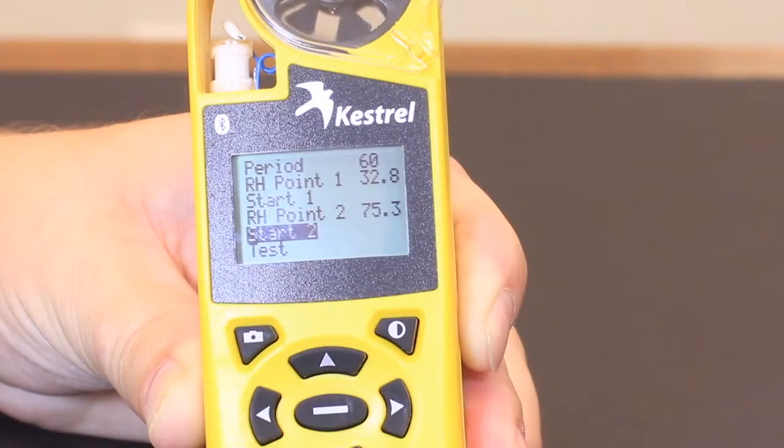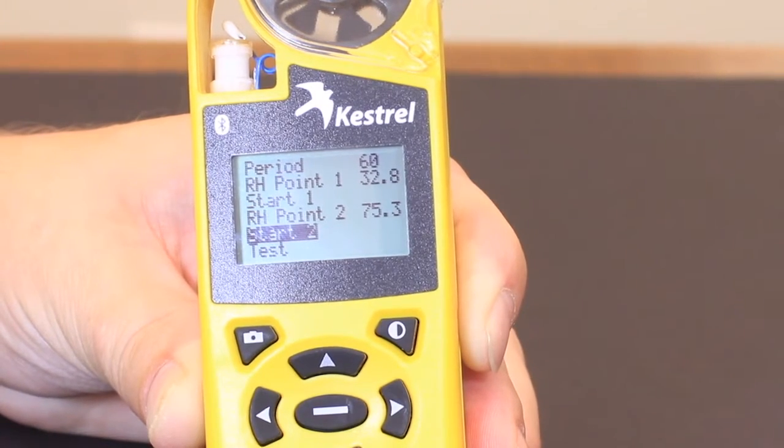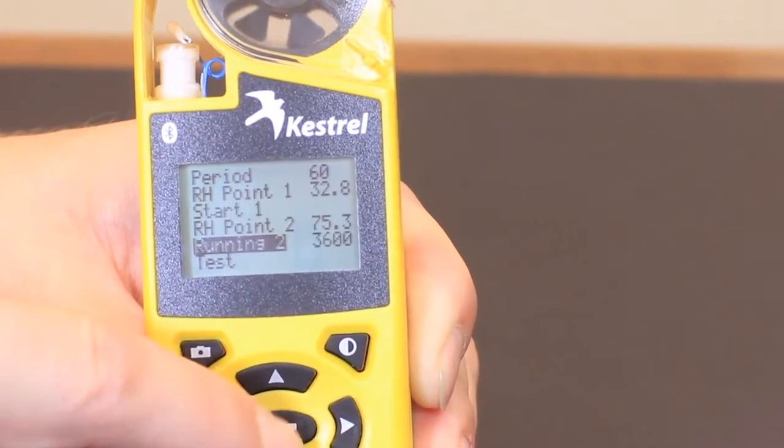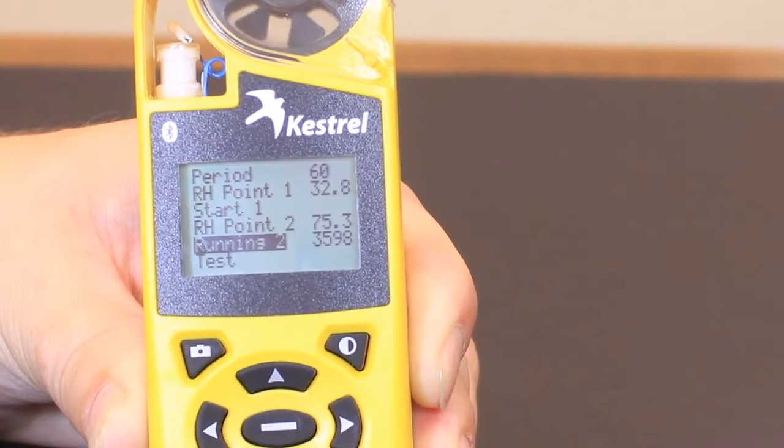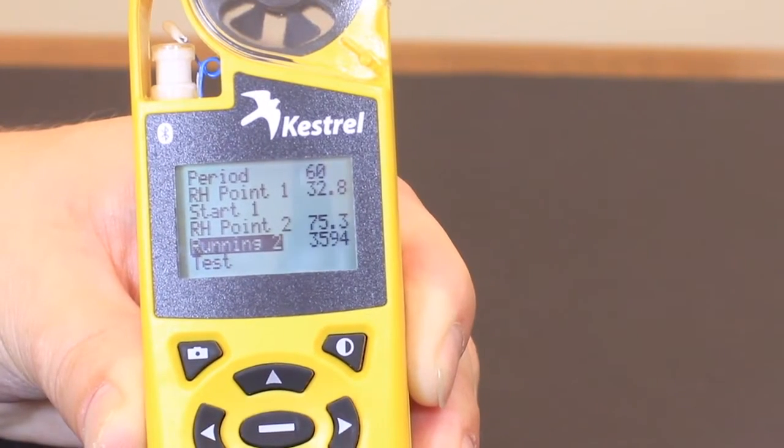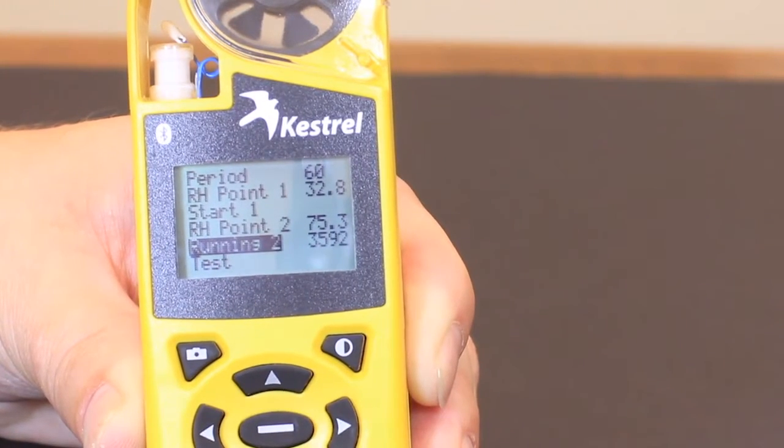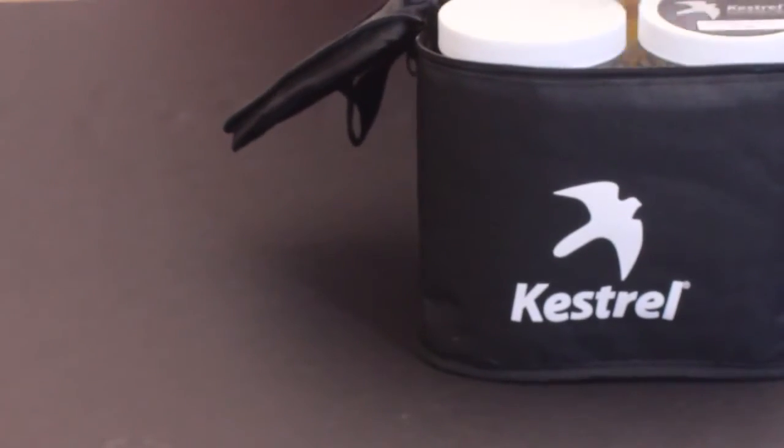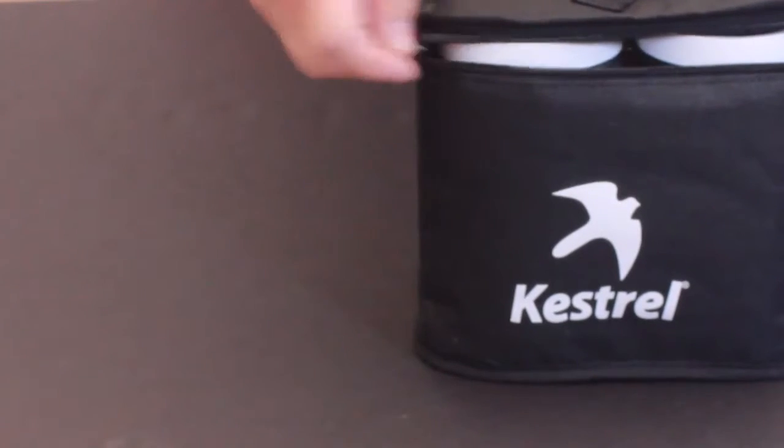We just pulled the 4500 from the first calibration chamber and now we're ready to proceed for the second calibration. We'll go to Start 2, hit the center button. Again it'll start counting down from 3600 seconds. We're going to take the Kestrel, put it now in the second calibration chamber, and wait an hour. We're going to open this up, put it in the sodium chloride chamber, tighten this up, and put it back in to leave undisturbed for another hour.